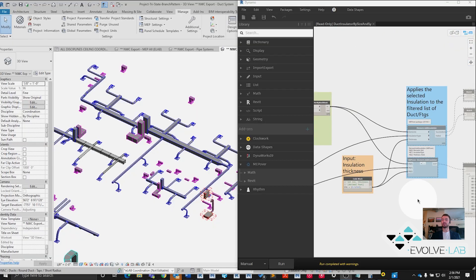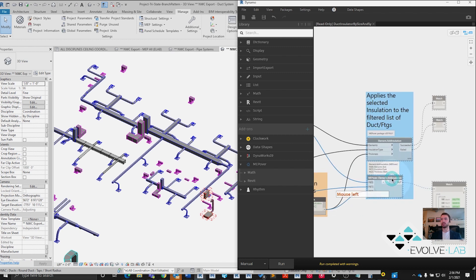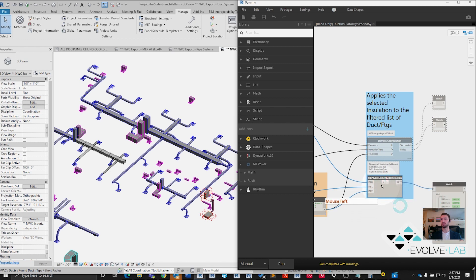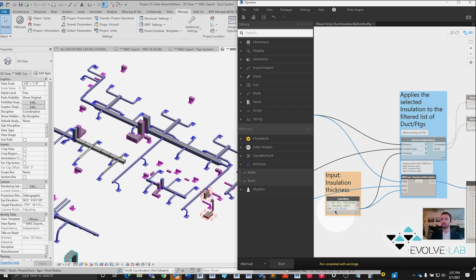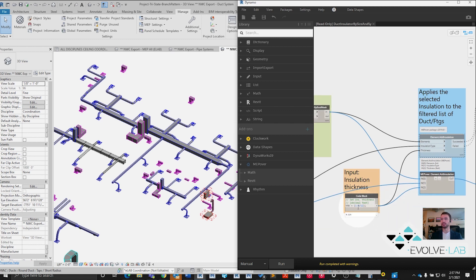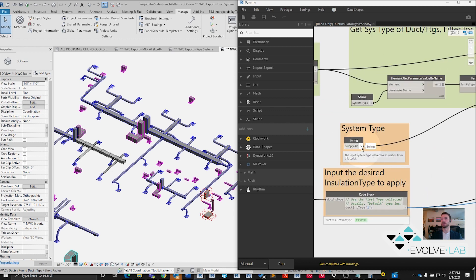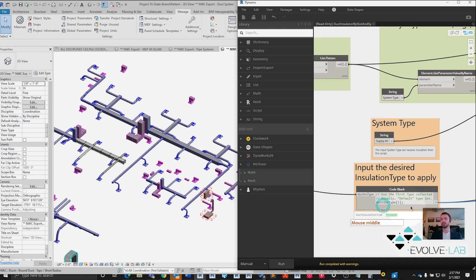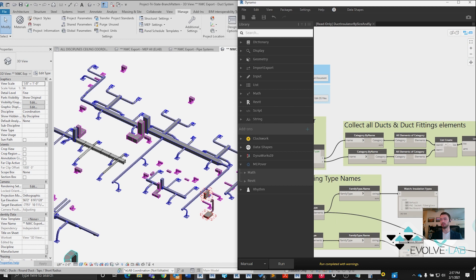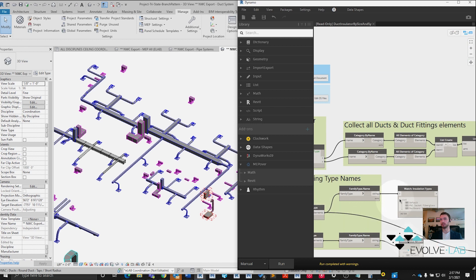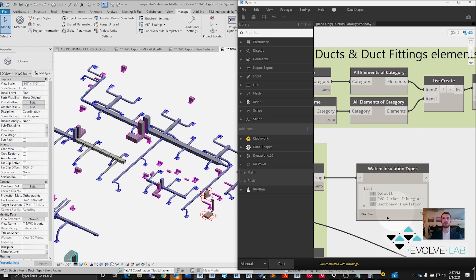Now that we have our script in a position where it's ready to be run, let's go ahead to those output nodes and unfreeze the Python node. Let's click unfreeze. The reason I'm doing the Python node and not the MEPover node is, if you guys want to use the script and don't have the package, you'll be using the Python node. Let's double check the inputs. We have an inch and a half insulation in decimal feet, so you divide by 12. We're going to apply insulation to supply air. And the insulation type is at the first index position of that list, which is PVC jacket fiberglass. I've gone ahead and split the windows here. I think we're ready to run. Excellent.